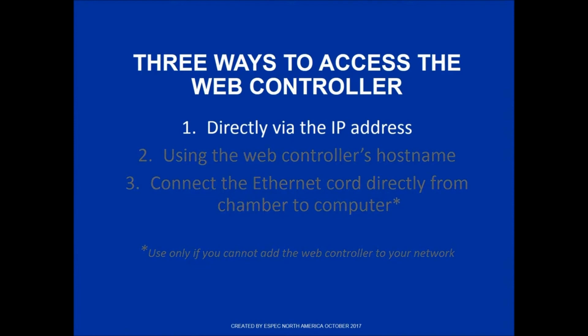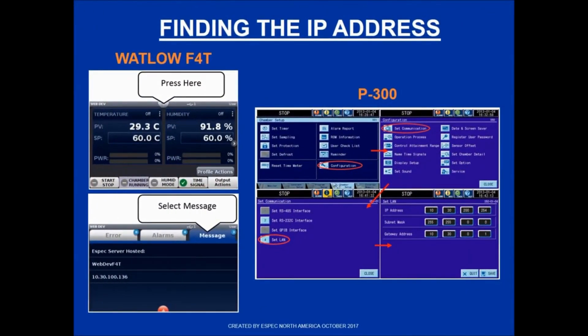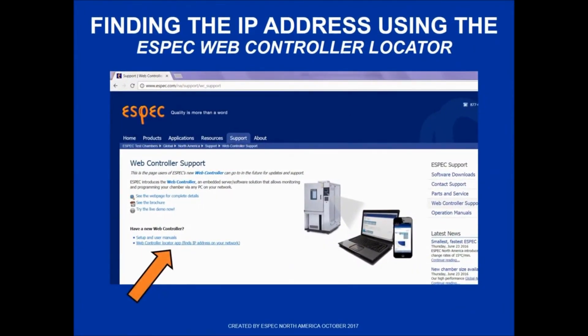The first method is connecting directly using the IP address. You can find the IP address by clicking through the on-screen menus on your chamber controller screen, as shown for either your Watlow or your P300 controller. You can also use the ESPEC web controller locator to find the IP address, which can be downloaded directly from ESPEC.com and installed onto your computer.